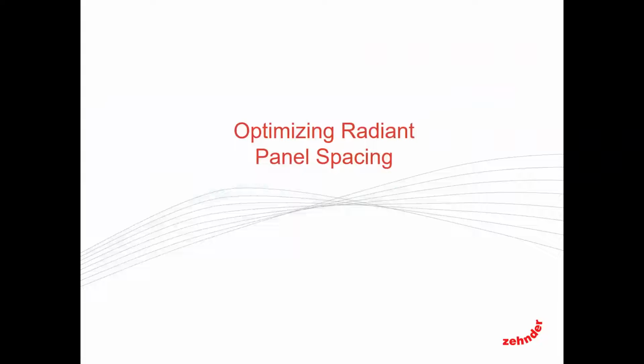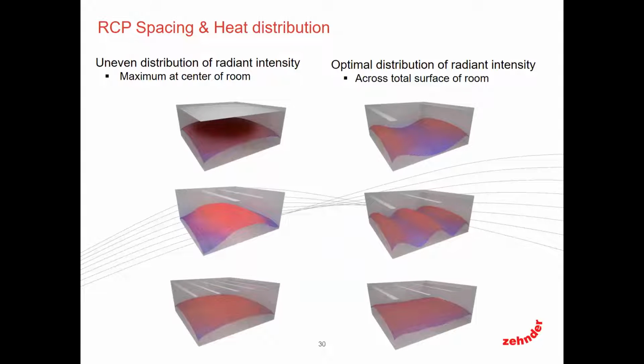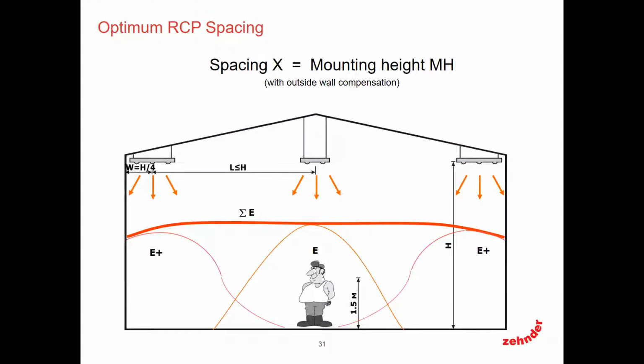All right, so let's talk about spacing and optimization. When we talk about covering a lot of the ceiling space, whether it's 30, 40, 50, 60% coverage of the ceiling, we have to have this conversation about spacing, distribution, and creating a comfortable environment for the occupants, right? Because we don't want to create spots where you would be uncomfortable, too hot or too cold. The general rule of thumb that I give everybody that simplifies this approach is to take the height of the panel that you're mounting off the floor, and that is generally your spacing from center line to center line of the panel. So if you're mounting the panels at 9 feet, 9-foot spacing from center to center is your maximum. Now, if you have more panels that take up more ceiling space, putting them closer is not a problem, but that's really the maximum distance you want to watch.